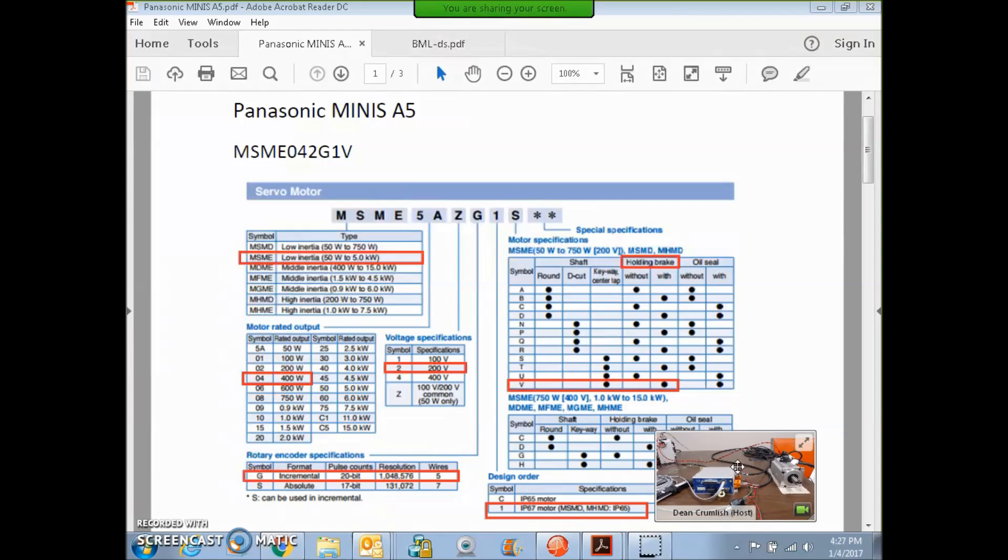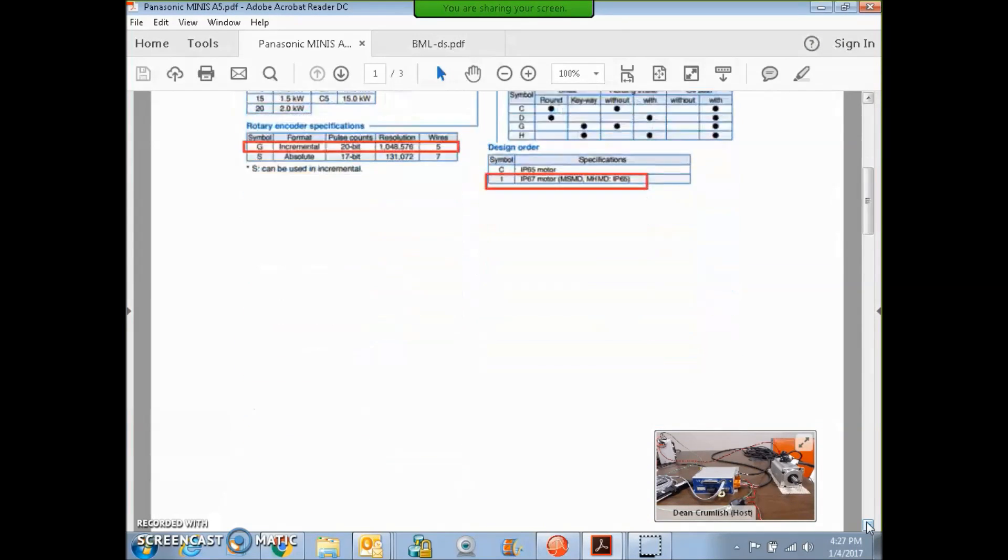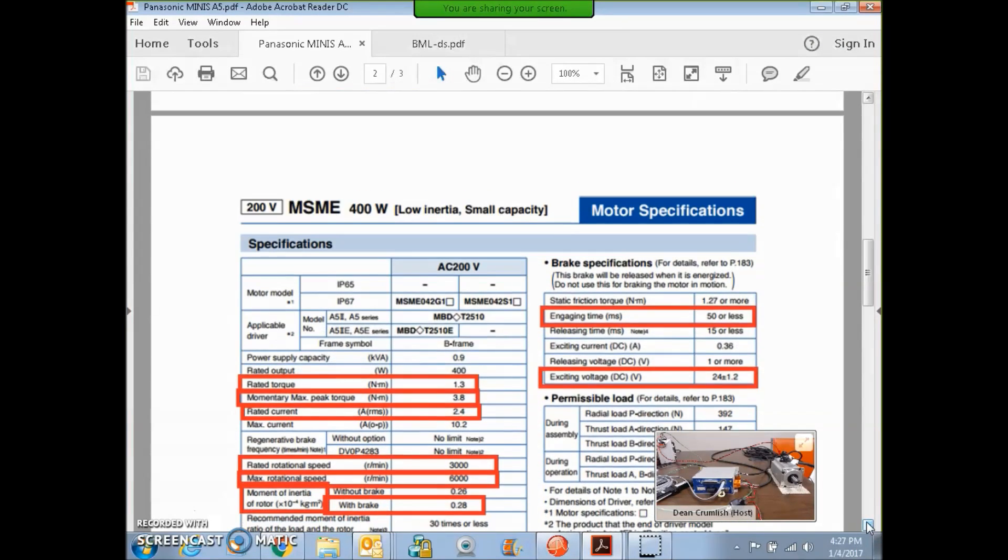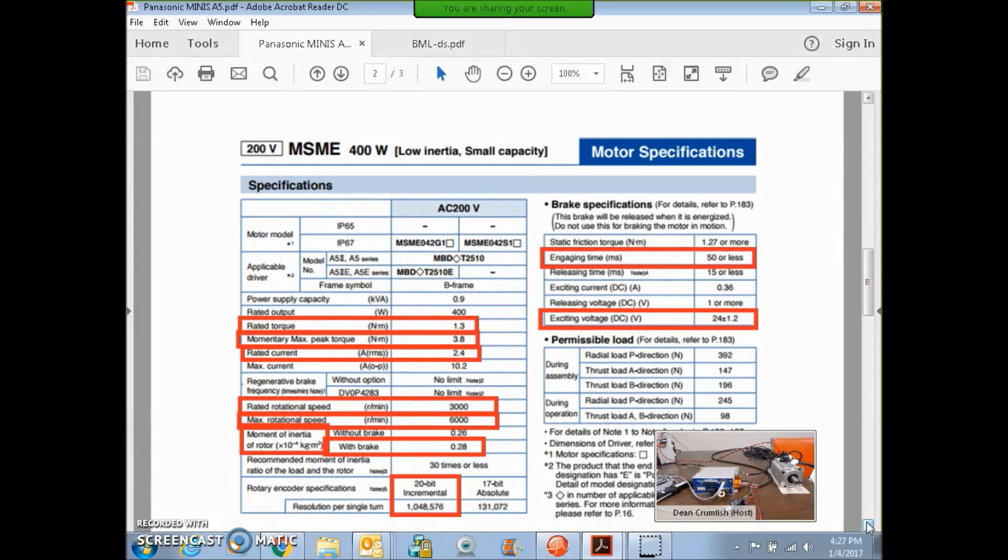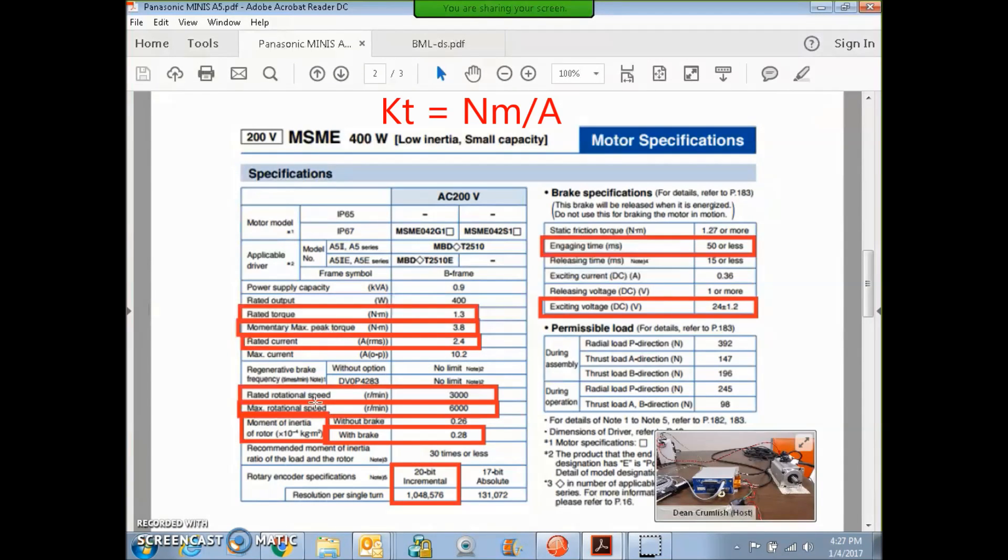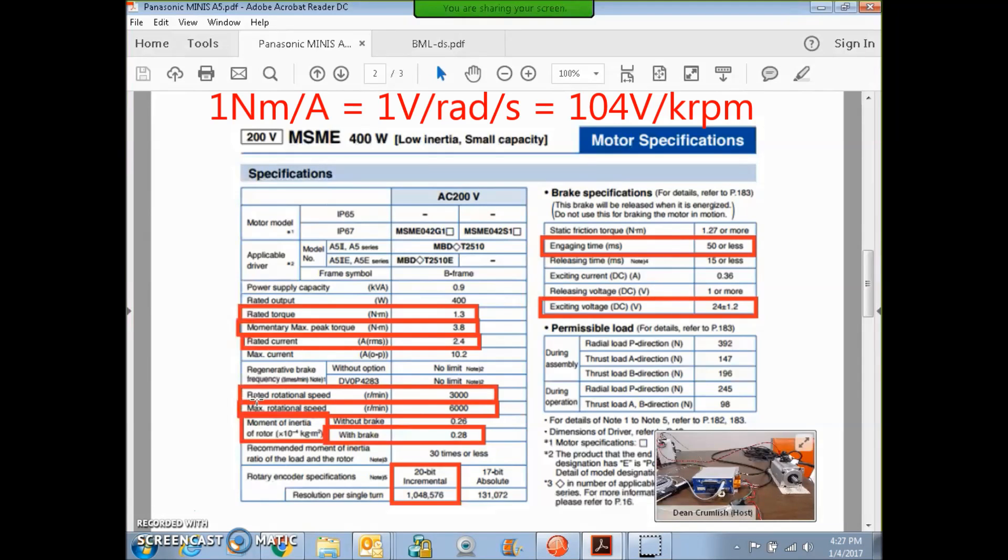We can see further in the manual for the motor, there is some motor spec information. They didn't show the pole count, but they got the rated and peak torque, the rated current in RMS. 1.414 times that is the peak current. I can get the torque constant. Newton meters divided by amps is the torque constant. From that, I can get the back EMF constant.